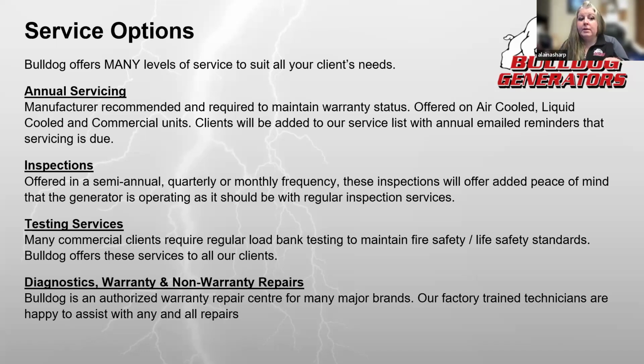So this thing needs to run till the very end. It's very important, if you deal with commercial buildings, that they do have these load bankings done. Typically the fire department will ask for these reports, because if that generator fails and they haven't had the proper maintenance or testing, they can get fined big time.